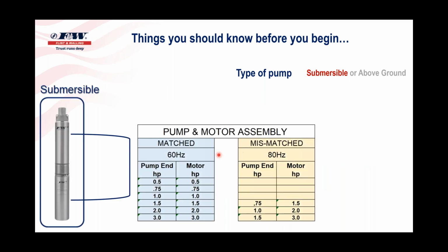But here's a couple examples. Over here on the left-hand side, those are all matched pumps and motors, all horsepower to horsepower, so they're going to always run at 60 hertz. But on this mismatched side, like I mentioned early on, we used to put a 3/4 horse pump in with a 1.5 horse motor, a 1 horse pump in with a 2, and a 1.5 horse with a 3 horse motor. So the pump end was rated at about half the horsepower of the motor, and we would spin that rascal at 80 hertz and get our performance out of it that way.